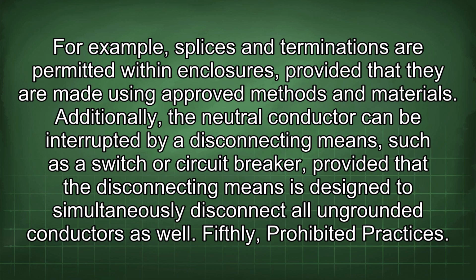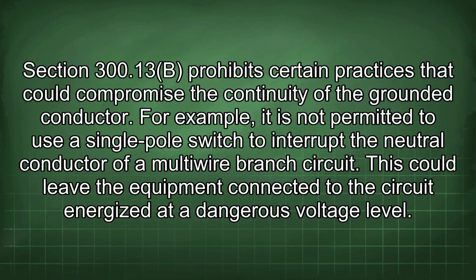Fifthly, prohibited practices. Section 300.13b prohibits certain practices that could compromise the continuity of the grounded conductor. For example, it is not permitted to use a single pole switch to interrupt the neutral conductor of a multiwire branch circuit. This could leave the equipment connected to the circuit energized at a dangerous voltage level.